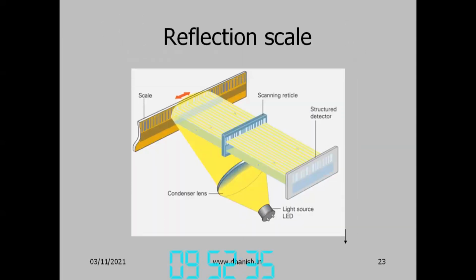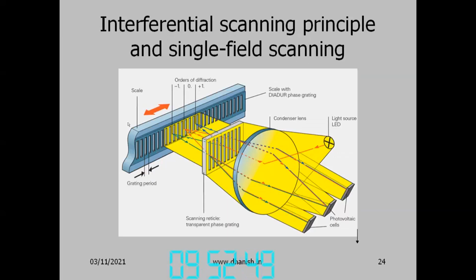Reflection scale works the same way, except that it is not transmitted through the scale, but it is reflected from the scale. So the scale is not glass. Interferential scanning and single-field scanning: it is reflected from the scale, and the interference happens after reflection. And of course, the counting is not manual. It's all through LEDs. They count how many lines are transmitted. They measure the intensities, so brightness increases, decreases. So they determine the minimum, maximum, etc. and then find out how much the displacement is.